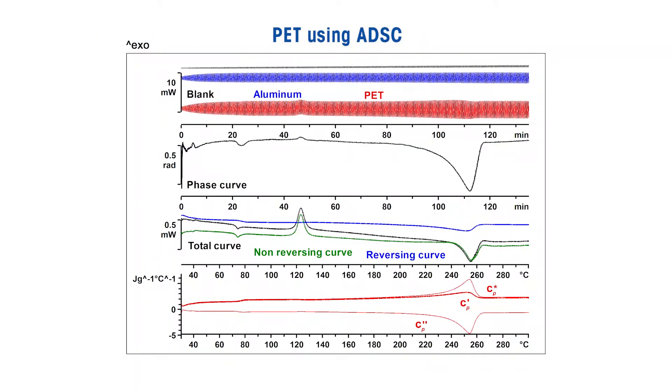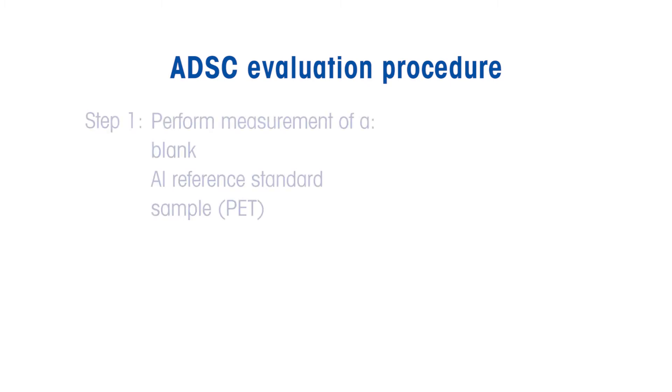In this video, I describe the ADSC evaluation method performed on a PET sample to illustrate the kind of questions ADSC can answer. This includes how to separate reversing and non-reversing phenomena and obtain accurate heat capacity values using aluminum as a standard. The procedure can be summarized in just three simple steps. First, perform measurements of a blank, an aluminum reference standard, and a sample.